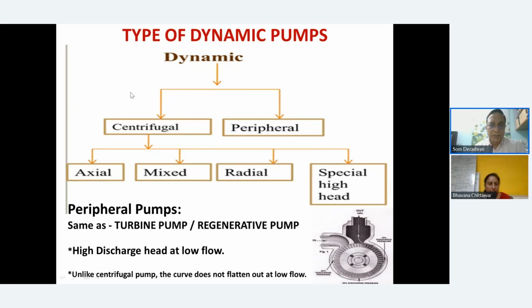where you have the centrifugal pump, which constitutes almost 80% of industrial applications. We're mainly concentrating on this type of pump. The peripheral pump, I've already told you, you see in this picture at the bottom right that the liquid is sucked in on the periphery, and then like turbine blades they move, and because it's concentric, it gets pushed out of the chamber here. This kind of pump is also known as a turbine pump or regenerative pump, and it has high discharge head and very low flow basically. Then you have axial, mixed, and radial pumps.